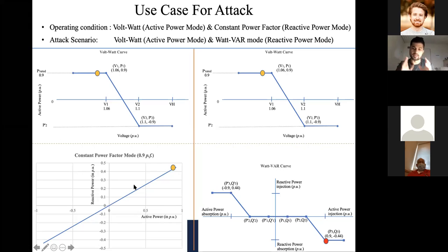So what happens now is the attacker is going to change the mode from constant power factor mode to watt-var curve, to watt-var mode. For the volt-watt, it's going to stay the same because there's only one option for volt-watt, and the attacker just leaves it as it is. So as you can see, V1, let's say it is at 1 pu, or even if it depresses, even if it goes below 1 pu, it is going to stay around this area. So it is going to be injecting 0.9 pu.